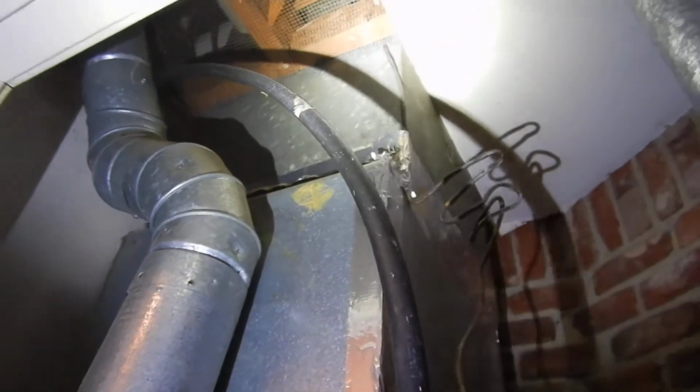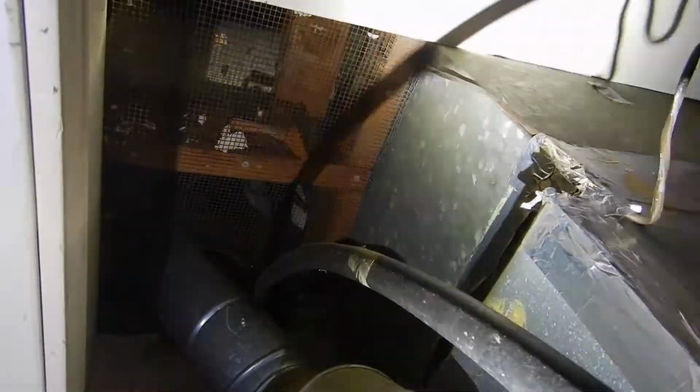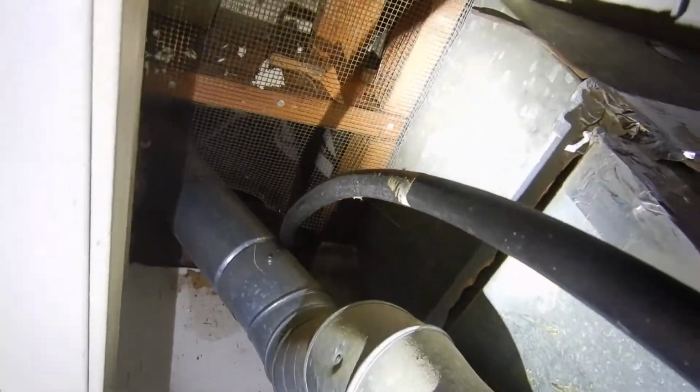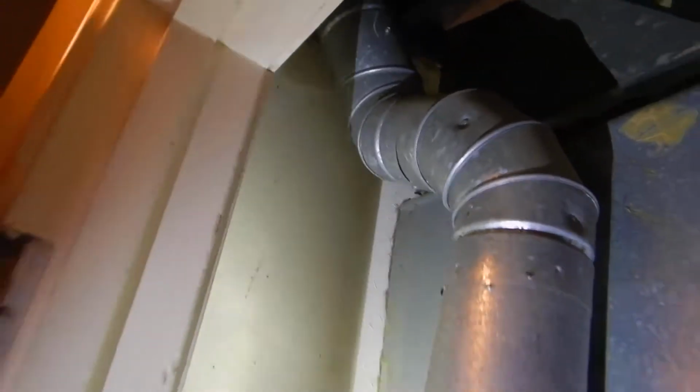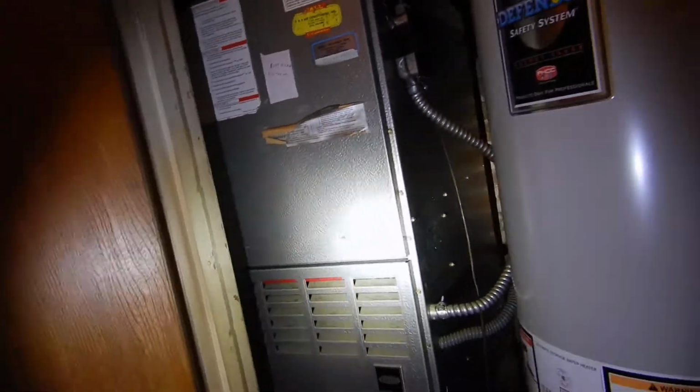First thing, and this goes for the water heater as well, our makeup air has a screen over the makeup air vent, and screens are no longer allowed. They used to be required, or at least they were deemed preferred. But today we don't want those. See how the debris is catching on there. When the attic gets re-insulated, we're going to have problems with all that.